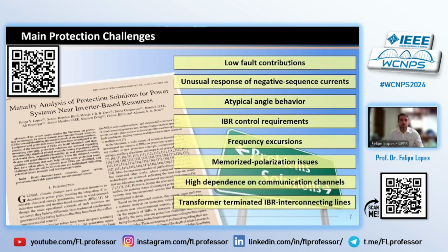like low fault contributions due to the presence of current limiters, the unusual response of negative sequence currents, for instance, because the controls suppress or change the patterns of negative sequence currents depending on the used grid codes. There is an atypical angle behavior, of course, because the controllers act changing angles and magnitudes. The IBR control requirements, and in this case, I mean the grid codes, we have seen that using different grid codes, the fault response can change.